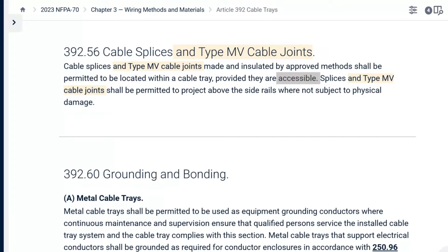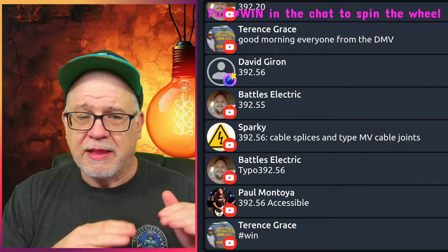There are other applications where it may be ran where you want to make splices in it, but it's just not acceptable if it's not accessible. It doesn't say readily accessible, just accessible. Well, you have to determine it is. So most of the cable trays that I deal with are going to be accessible, right? A lesser threshold than what you would get for readily accessible. This is just accessible, right? So if you can get to them, that's a requirement.